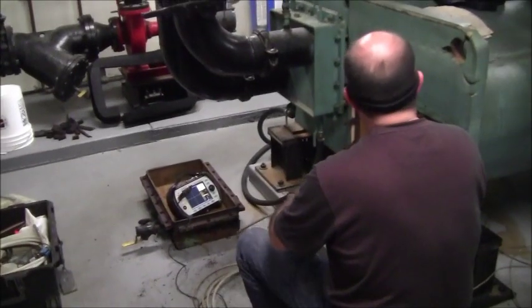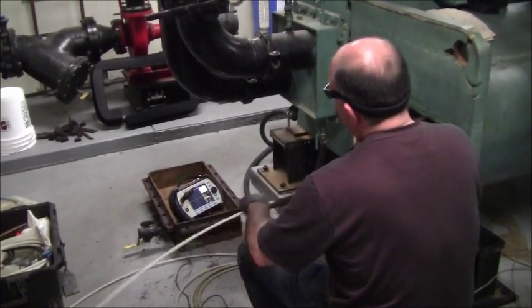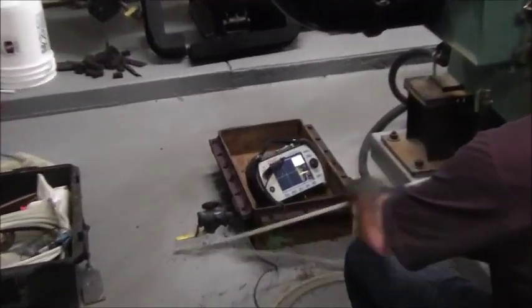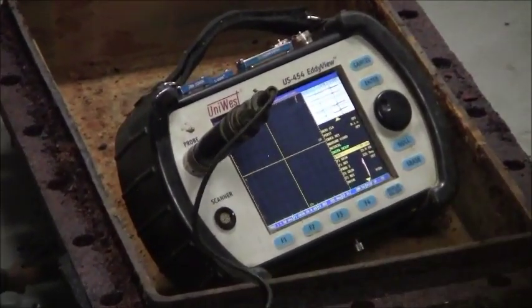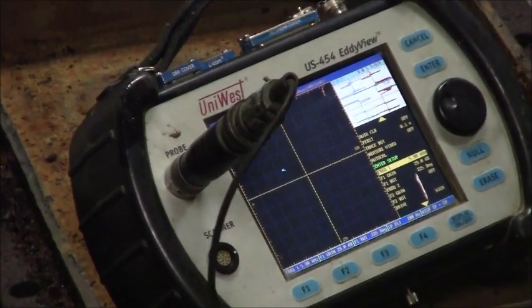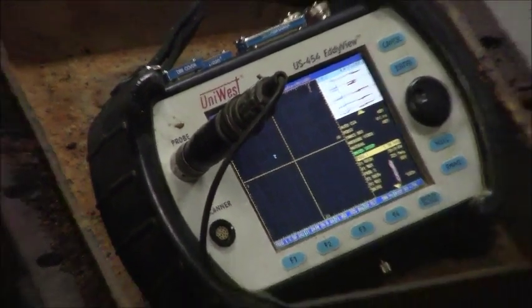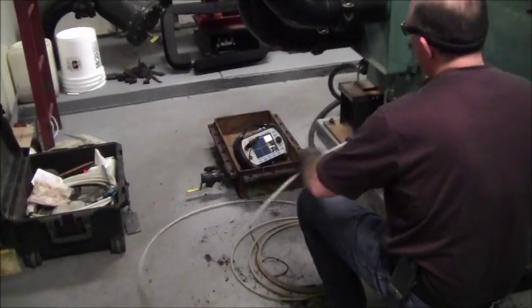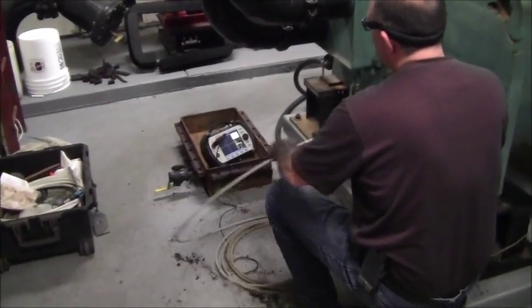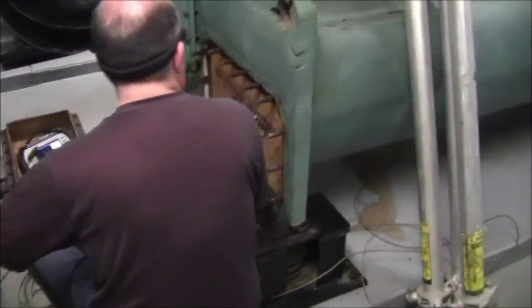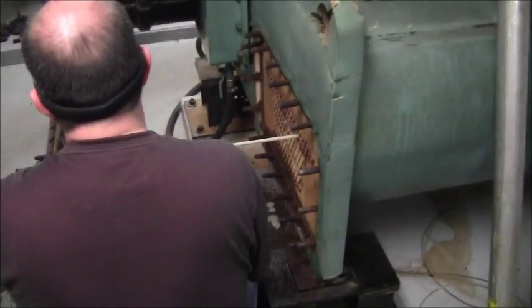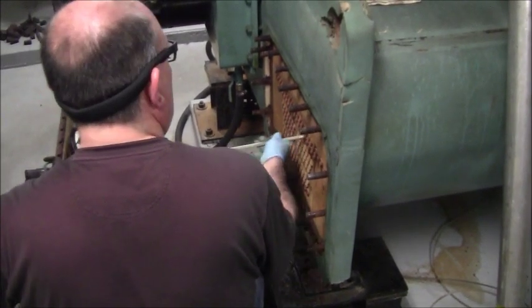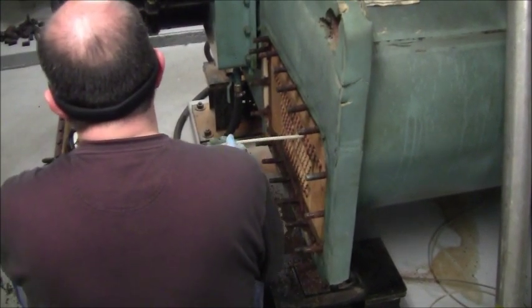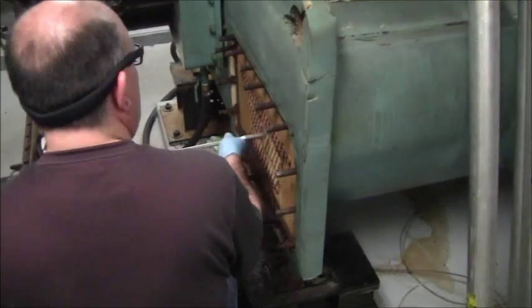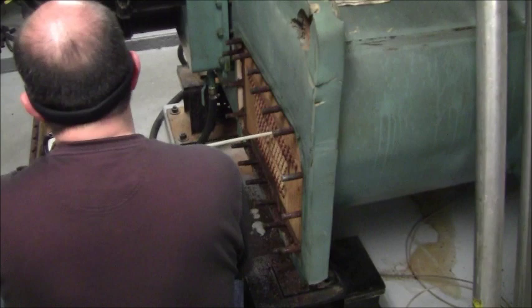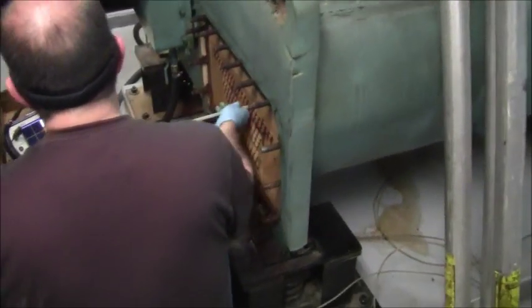All right, we're doing eddy-current testing here on this chiller. There's the eddy-current machine right down there on the floor. And you can see the readings that are being displayed there for the technician to see. Here he is taking the eddy-current testing rod, putting it down through the tube sheet and into the tubes through the entire length of the chiller. He's got it marked off so he knows exactly how much distance he needs to go in through the chiller. And then he's methodically going one tube at a time.